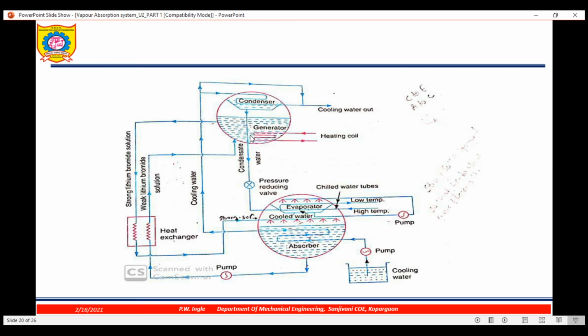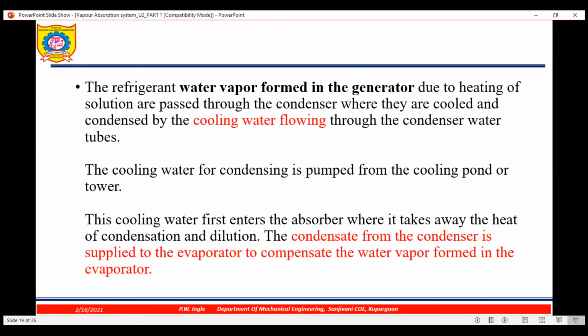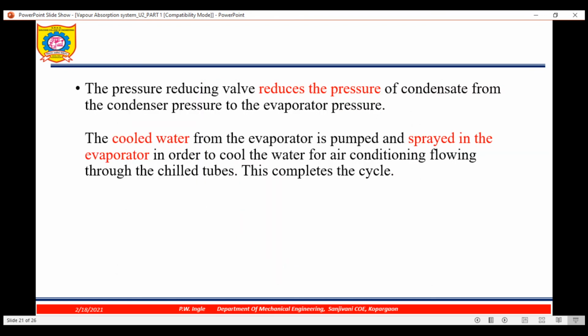Now refrigerant which gets condensed will be reduced in pressure by a pressure reducing valve and it is supplied to where? It will be sprayed over the water tubes, or chill water tubes. Then next, the cooling water first enters the absorber where it takes away the heat from condensation and dilution. The condensate from the condenser is supplied to the evaporator to compensate for the water vapor formed in the evaporator. Okay. Now the pressure reducing valve reduces the pressure of the condensate from the condenser pressure to the evaporator pressure.